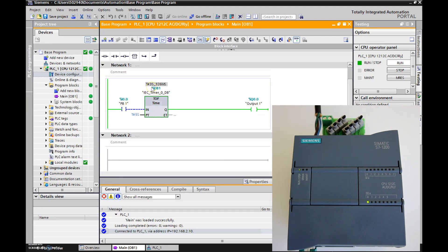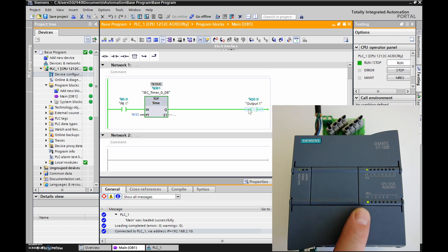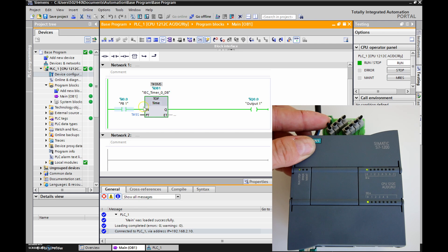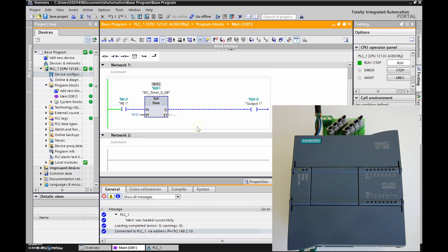You can see the timer counting: three, four — and it turns off right when it gets to five. One more time for the off-delay: we enable the timer, the output turns on right away, and you can see the LED is illuminated. Now we stop logic continuity to the timer — the off-delay timer takes some time to revert back to its rest state, meaning the output will be off in rest state. We take away logic continuity and it times out: one, two, three, four, five.